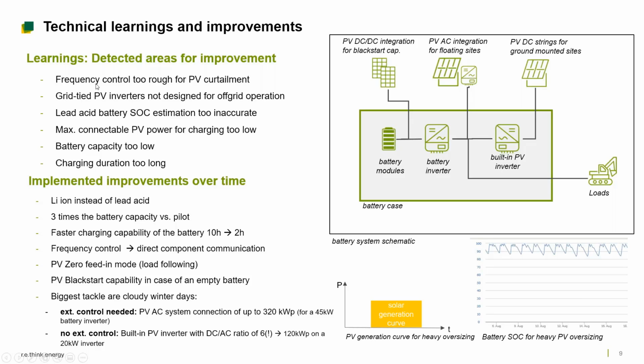We found out that for us, the frequency control of the PV inverters is too rough a control mechanism to really control the PV curtailment, because these grid-tied inverters, which are used for the solar parks, are not really designed for off-grid operation. Next is that the lead-acid battery SOC estimation is too inaccurate over time. The SOC estimation drifts apart after a while, which is not really suitable to have reliable SOC information.